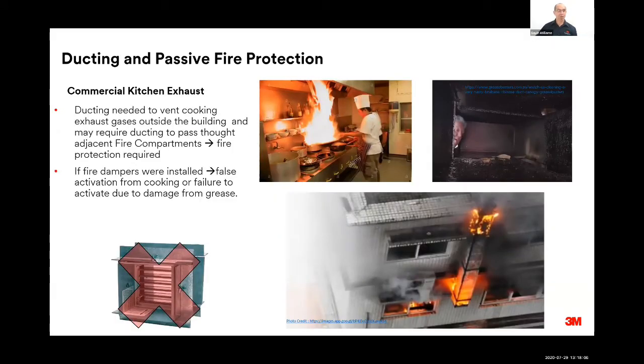However, there are quite a range of types of ducts where you cannot use dampers. They just don't work, or would impair the functionality of the duct. An example of that is kitchen exhaust ducts. So there's some issues there. If you had fire dampers, they might inadvertently be activated due to the hot gases from cooking and not necessarily a fire, and that could cause problems for the kitchen. And additionally, the sorts of materials that accumulate in kitchen exhaust could potentially impair the operation of a fire damper. The mechanism could be blocked and therefore may not work in the instance of fire. So in this case, fire dampers are not to be used in those particular ducts. So that raises the question: how then do we restore the fire resistance rating when that duct passes through other compartments to get outside of the building?